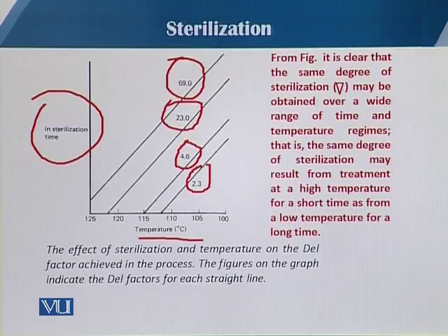These are the different Del factors with respect to different temperatures. This graph shows the effect of sterilization time and temperature on the Del factor achieved during the process.